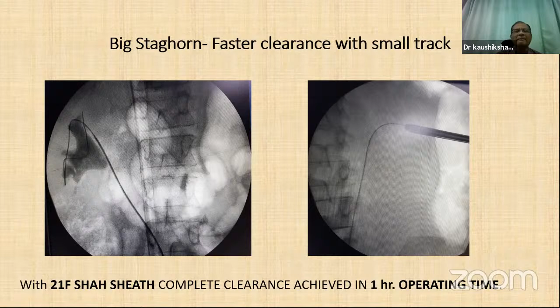The salient advantage of the sheath is it's very easy to introduce. It is a one-step dilatation with a sheath insertion, the way Dr. Madhu Agarwal has mentioned. It reduces the operating time and the radiation exposure. There are minimal chances of opposite wall perforation, it is ergonomic to handle the sheath, and the small sheaths like 12, 15, 18 are very sturdy, and it has replaced the other mini PCNL sheaths.